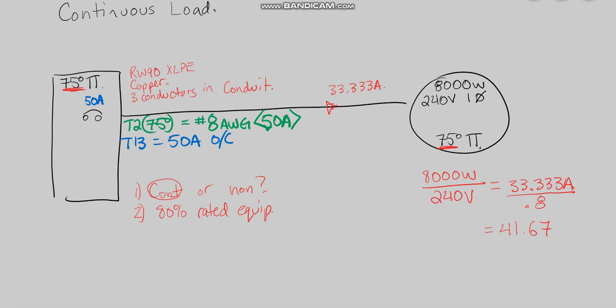When we're doing these branch circuit calculations, step one should always be, is it a continuous or non-continuous operation? That's dependent on what the load is doing, how much time is it running for. The second question, is it 80% rated equipment or 100% rated equipment? That will help us determine whether or not we're going to apply this 80% correction factor to our load to inflate to a higher minimum capacity to select a larger conductor, which leads to a larger 50 amp overcurrent.